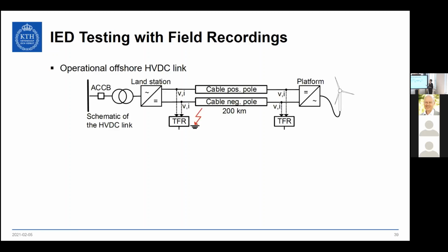The last part about the protection topic is field testing. We have to keep in mind that all the testing before is done on a real-time simulation, which means an engineer has to program that simulation. That can come with simplifications, aspects related to how you program the actual program, maybe computation power as a limiting factor, sampling, and so on. So it's good to complement these results with field recording tests.